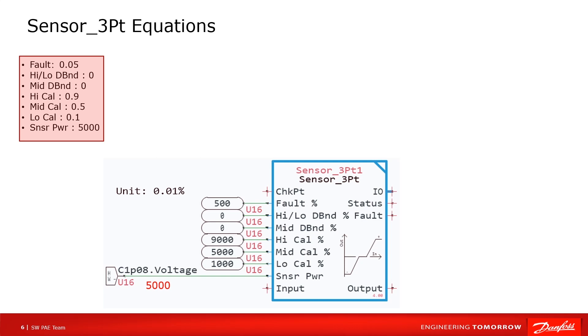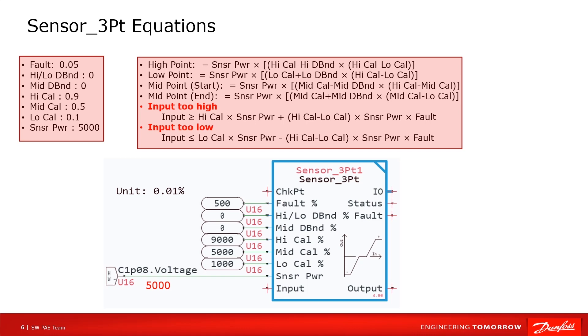Unit of these parameters is 0.01%. So we can take 0.9, 0.5, and 0.1 into formulas. These formulas can be found in user manual. After calculating, we can get the high point 4500, middle point is 2500, low point is 500.